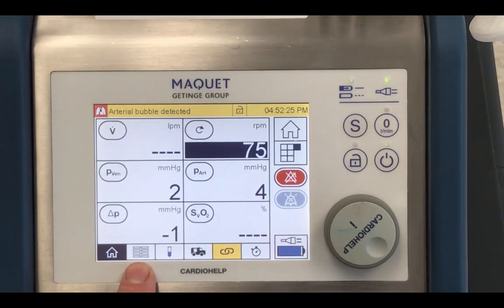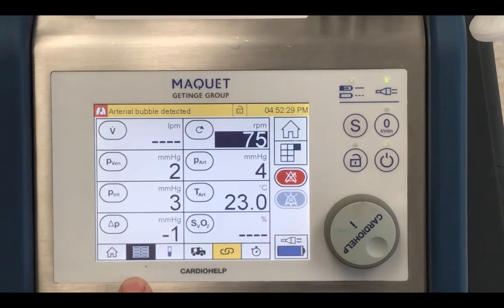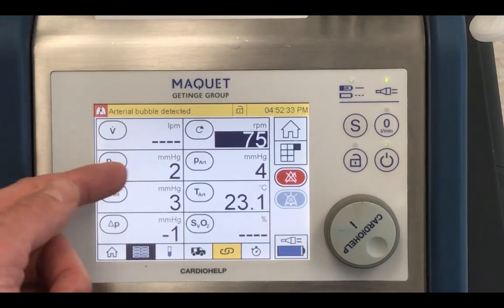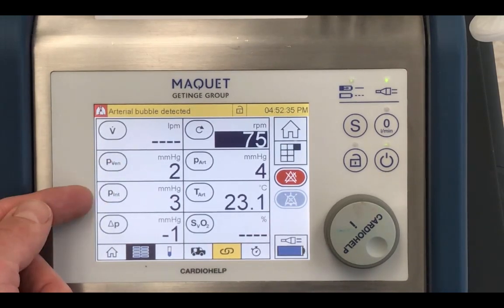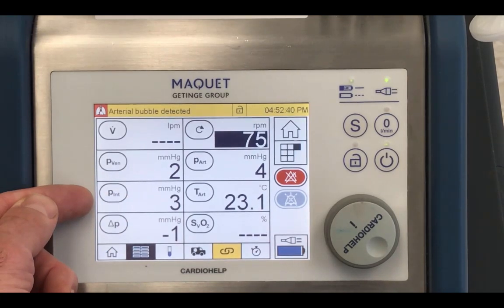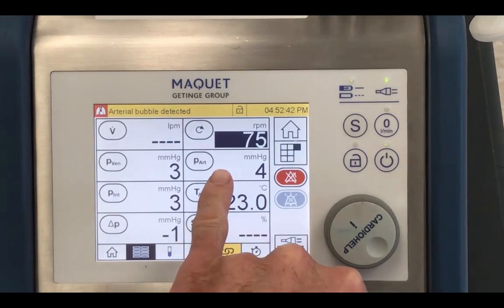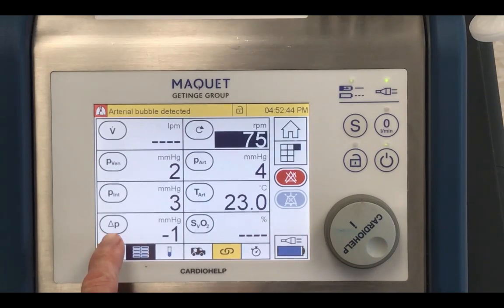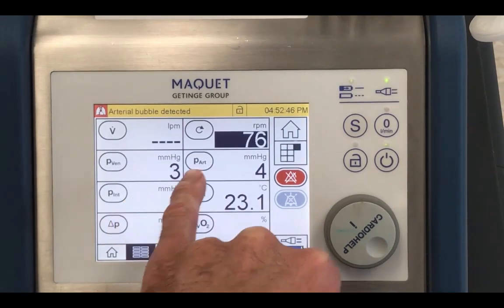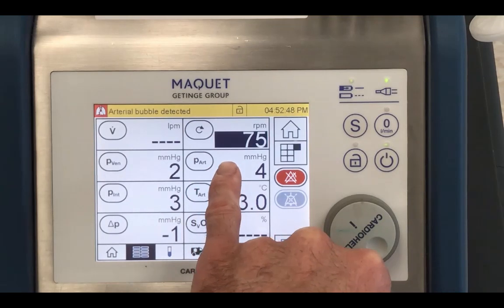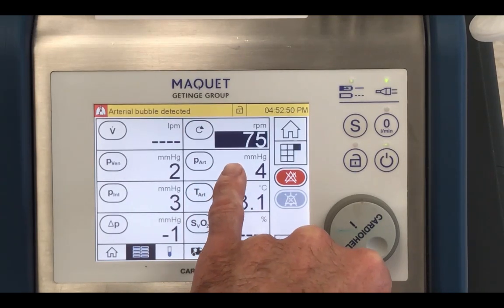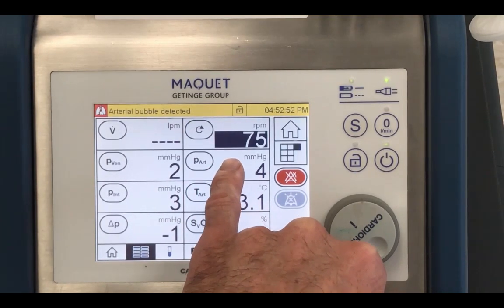If you want to see more than these 6 pieces of data, then you can select this button here, and you go into that, and it makes the boxes smaller and gives you more data. So we have flow, P venous, the pressure of the venous line, P INT, P internal, which otherwise is known as the premembrane pressure. You have the delta P, which is going to be the difference between the internal and the arterial, because the P arterial in Cardiohelp speak is equivalent to the post-oxygenator pressure in every other ECMO system.